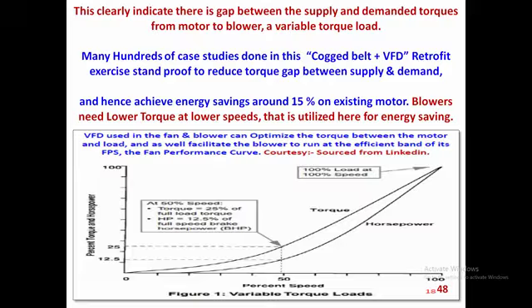By facilitating the VFD, the load needs lower torque only, especially blowers at lower speeds. If the VFD is made to address the lower torque, definitely 15% savings is there on the existing motor. This is where a VFD-coupled motor along with the pulley and belt combination gives around 15 to 20%. This is a cakewalk. Many IT buildings are doing it now instead of going for EC fans.